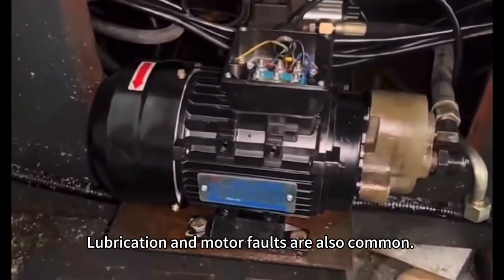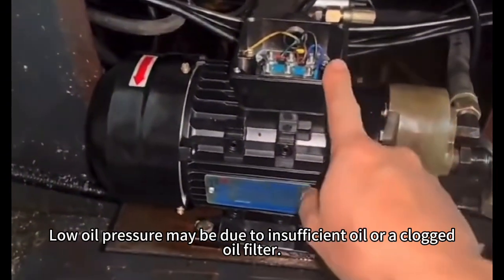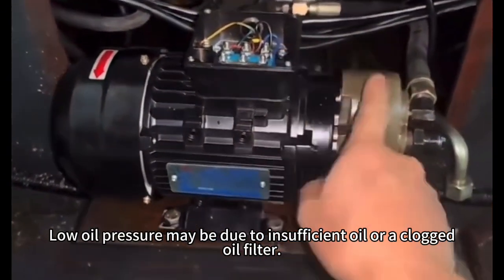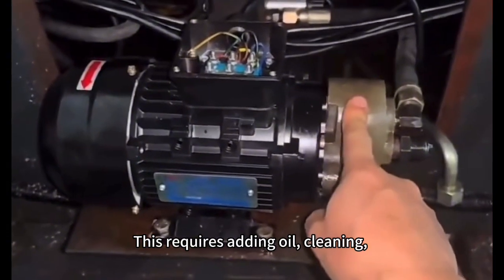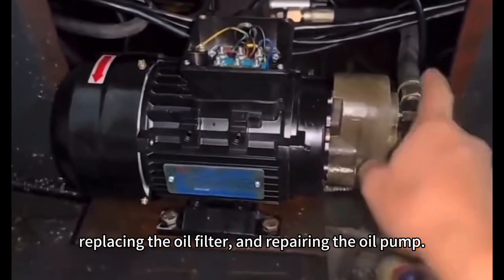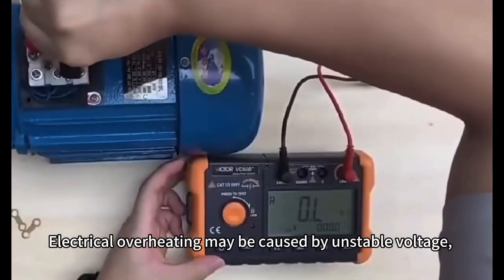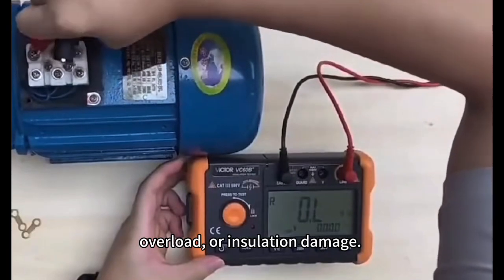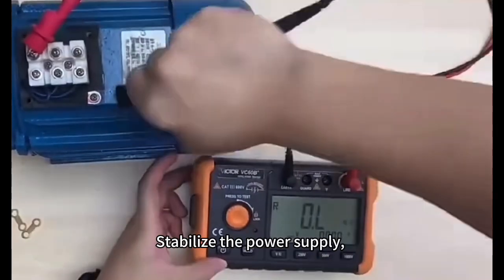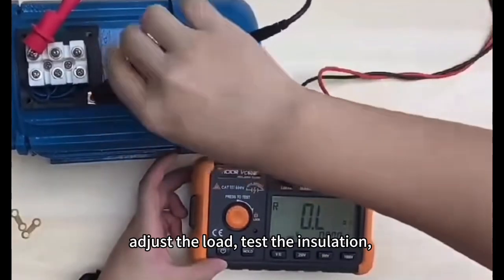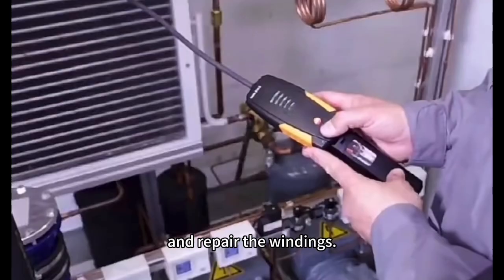Lubrication and motor faults are also common. Low oil pressure may be due to insufficient oil or a clogged oil filter. This requires adding oil, cleaning, replacing the oil filter, and repairing the oil pump. Electrical overheating may be caused by unstable voltage, overload, or insulation damage. Stabilize the power supply, adjust the load, test the insulation, and repair the windings.